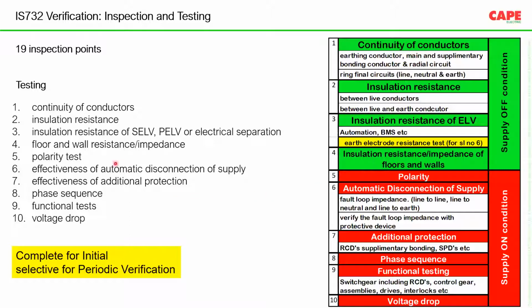Now you can look at test number 6, effectiveness of automatic disconnection of supply. Out of these 10 tests, 4 tests are in off condition and 6 tests are in on condition. That means you really need the power supply to undergo these particular tests. And all these tests and inspection points are applicable during the initial verification. Initial verification means immediately after completing an electrical project, immediately after completing your wiring, all the 19 inspections and 10 tests are applicable. Of course, upgradations are happening on the standard, and now more advanced things are coming up. Whereas for periodic verification, you cannot do all these things, especially continuity resistance measurement of wires. Periodic inspection is very difficult. You cannot do all the tests of serial number 1, but you can do only a few of them.